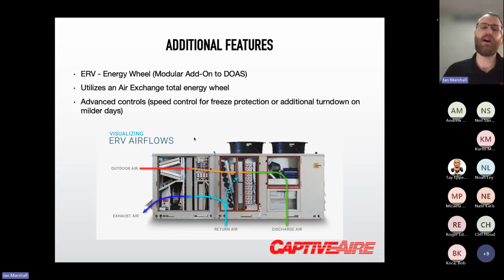This is its own pre-treat, or a stage of heating or cooling before the air enters the DOAS, to essentially recover energy from the exhaust airstream if you have the exhaust running through the building. We have some advanced controls for wheel speed control and frost protection on that wheel as well. It is available as an option. It does add a little bit of lead time and some upfront cost, but I understand it's a lot of times required by code, so it is available.